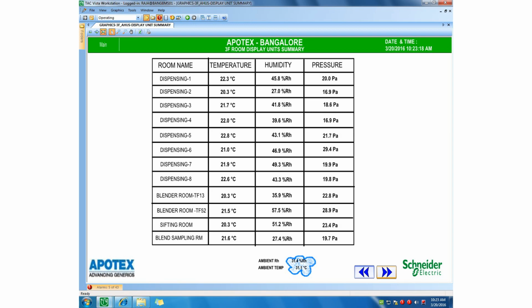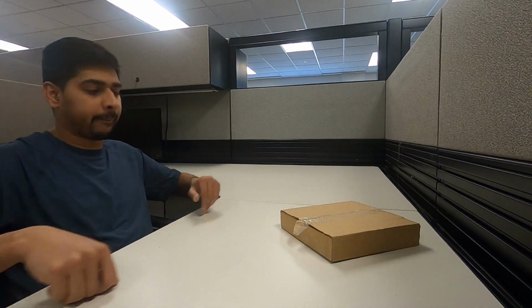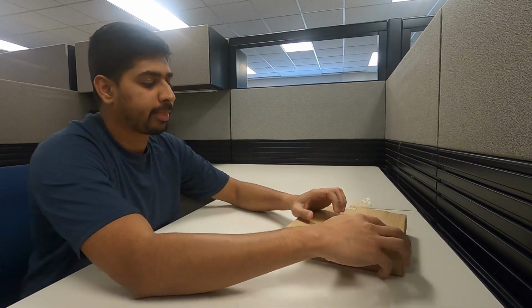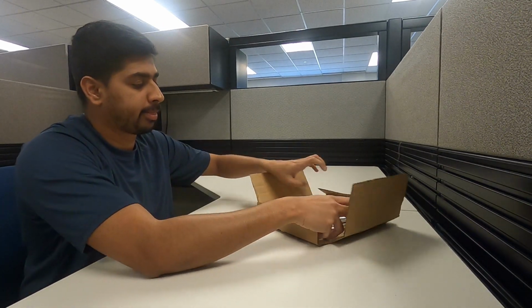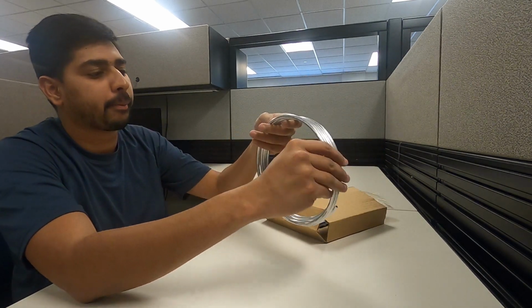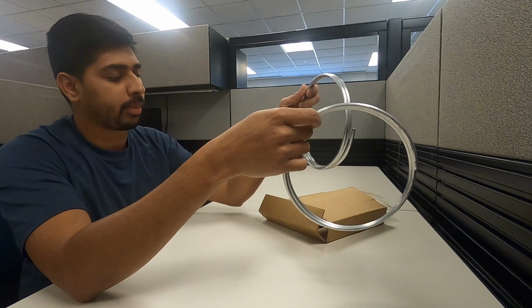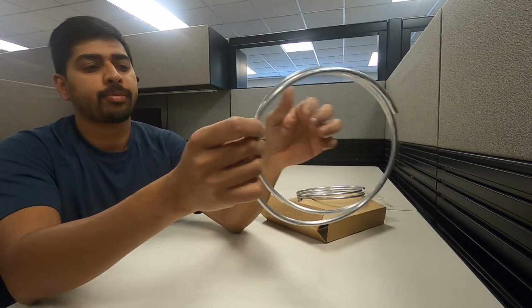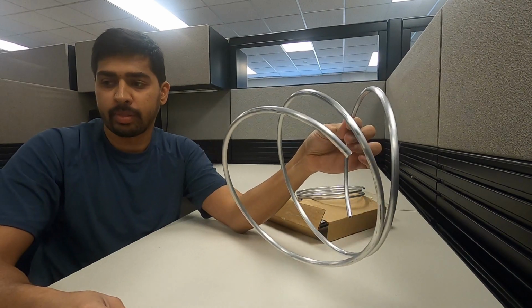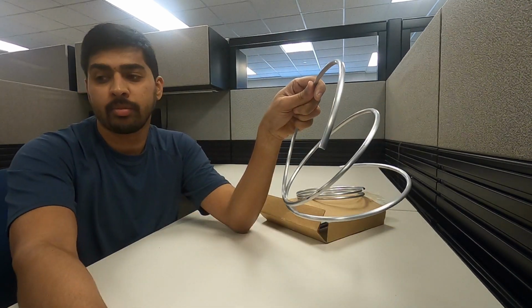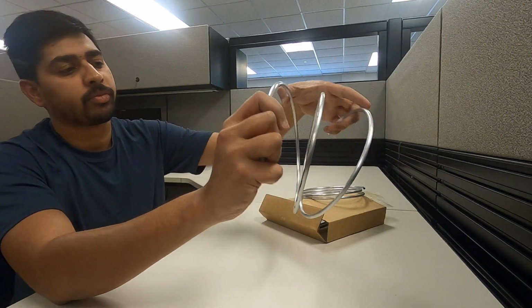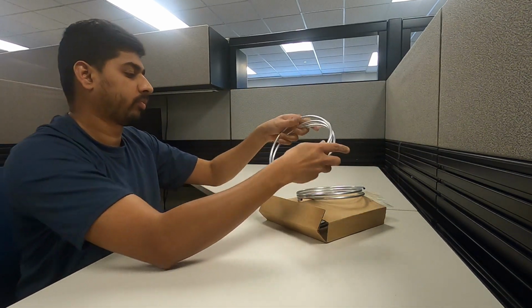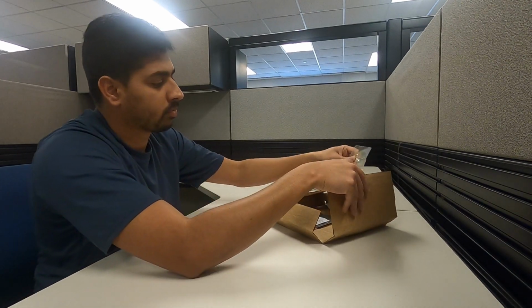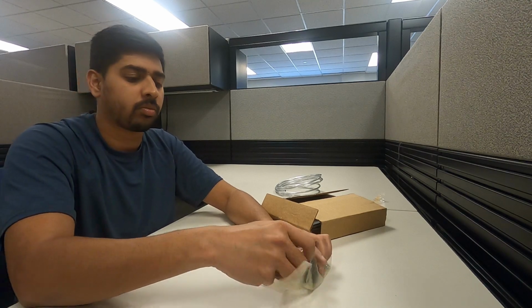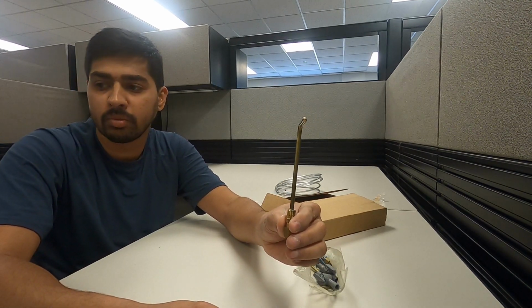Now, for the selection process for the pressures: pressure sensors need accessories such as pickup tubes and metallic bends to get the reference of the pressure difference. So it will have a high and a low tube, but where do you pick up the high and low tube from? Air? You'll need pickup tubes. When it comes to wet pressure differential sensors, you will need pickup tubes not to get air, but to get water. So it will be metallic fit-out tubes going into the sensors.